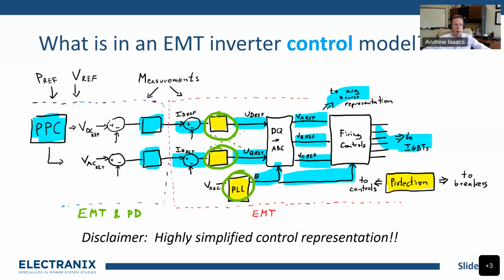These all have to be very quick and very accurate, and you'll find these are imperfect in any converter. These are implemented a little differently, maybe better or worse, and may respond slightly differently to different types of phase angle changes, different types of faults, etc. And the way that they respond and the way that they are integrated with something like these fast protection algorithms, which can be quite sophisticated actually. They're looking at moving averages, and they're looking at vector representations drawn out of non-60 hertz or transient or messy signals to try and pick out peak, max voltages and things like that.